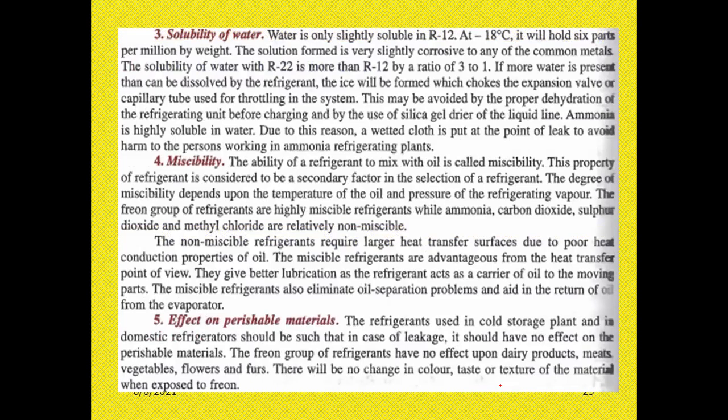Therefore, the solution is very slightly corrosive to any common metals. The solubility of water may differ for R-12 and R-22. The solubility of water with R22 is more than with R12 by the ratio 3:1. If more water is present, it cannot be dissolved by the refrigerant.